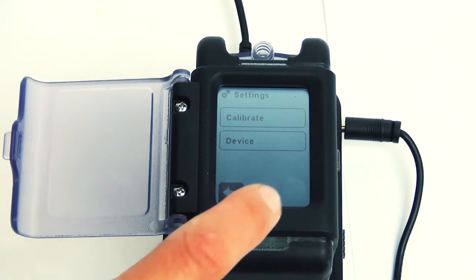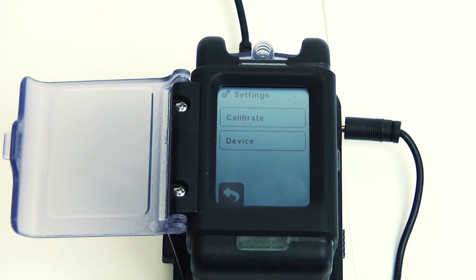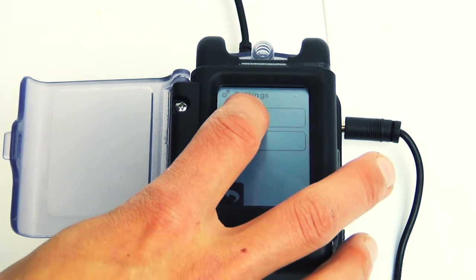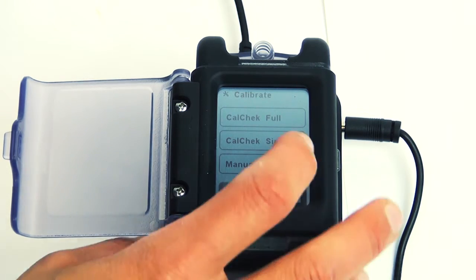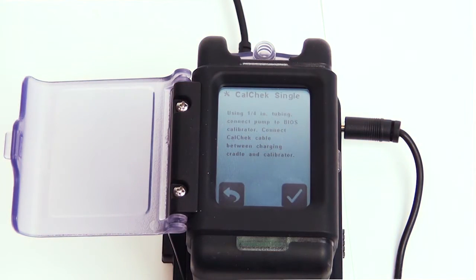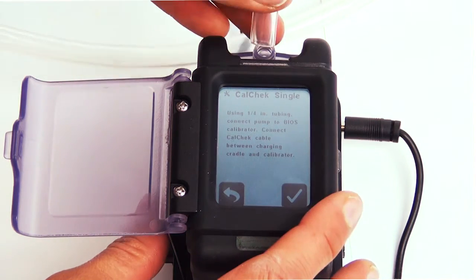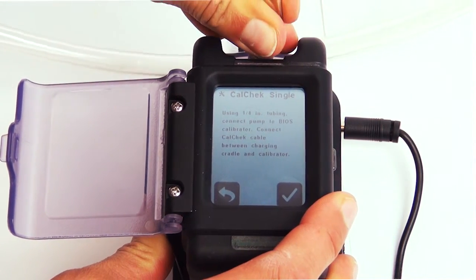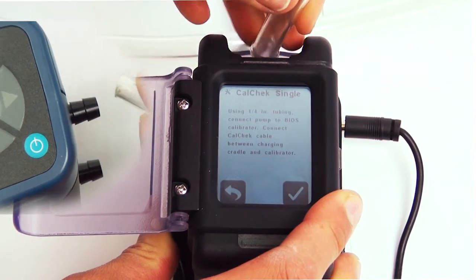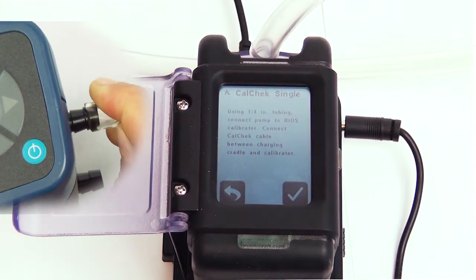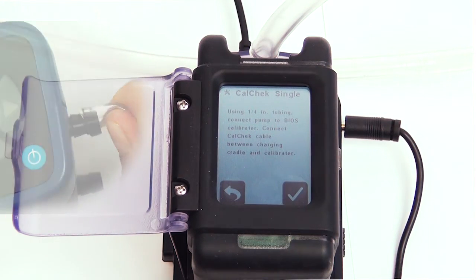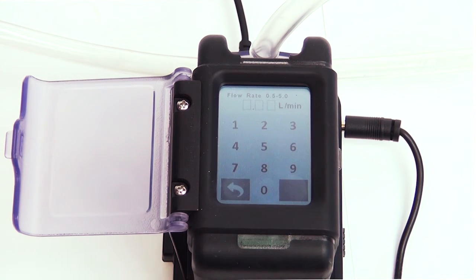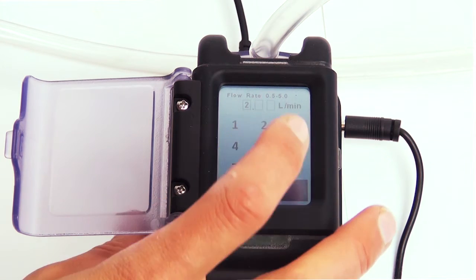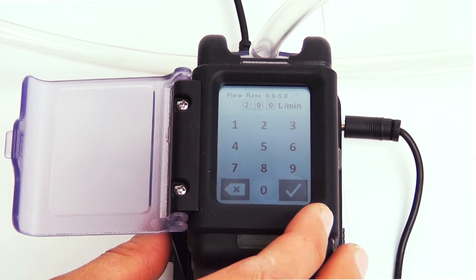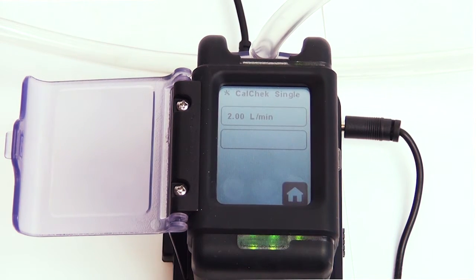Press the Settings key on your SKC AirChek Touch pump. Press Calibrate and then CalChek Single. The pump will prompt you to connect your calibration train or tubing with filter media from the pump to the Defender suction port. After you have connected your tubing, touch the check mark to accept the CalChek selection. Now enter a desired flow rate and touch the check mark to accept. The pump will start to run.